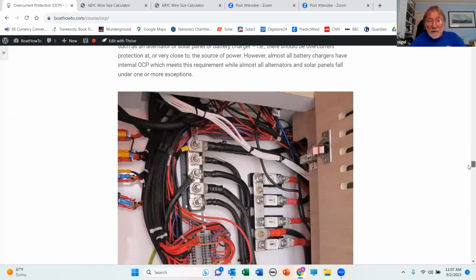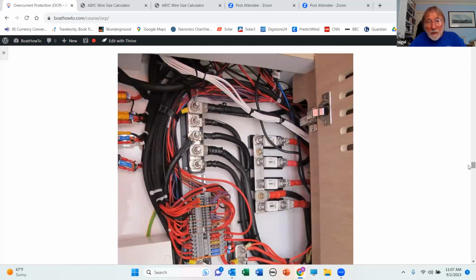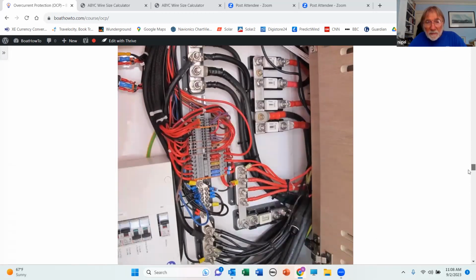And now we've got a fairly common scenario. Is it this one I want to look at? Yeah. We've got a bus bar here. We have a feeder conductor coming in from the battery. We have a fuse on the feeder conductor, which hopefully there's another one at the other end, the battery end, because otherwise this is totally non-standards compliant. And then we've got all of these conductors coming off the bus bar to loads. And then we've got this little conductor here.